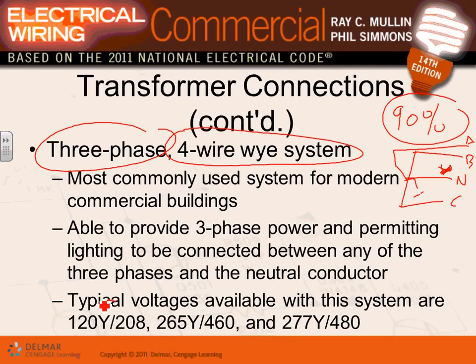In the US, here are the voltages that we use for it: 120/208 and 277/480. That's probably 90% of what the buildings will be wired with, and actually out of that 90, I would say 80% of them will be wired with this voltage, because it's the most efficient voltage that we use in the US. The most efficient low voltage that we use.